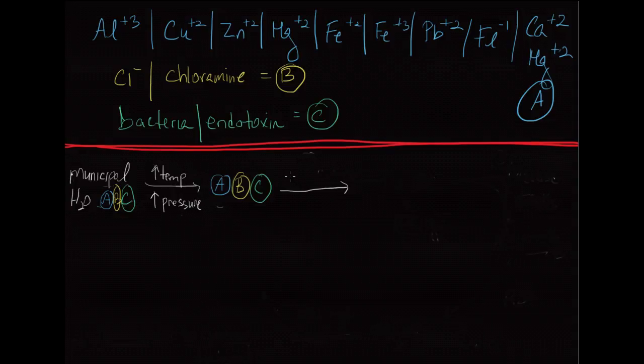One of the first things we'll get across is a softener. Every dialysis unit has a water softener because the water that it receives is going to be filled with lots of calcium and magnesium. If you don't eliminate this calcium and magnesium, you're going to have problems with the remainder of your water purification system downstream. You need them out of the water right away so that the rest of the water purification system works.